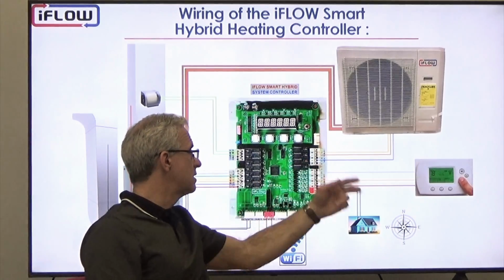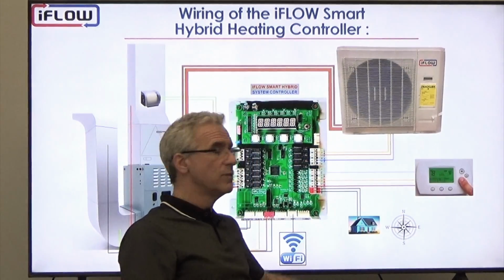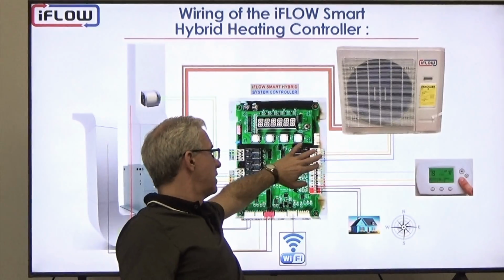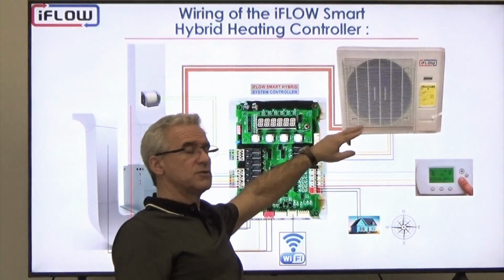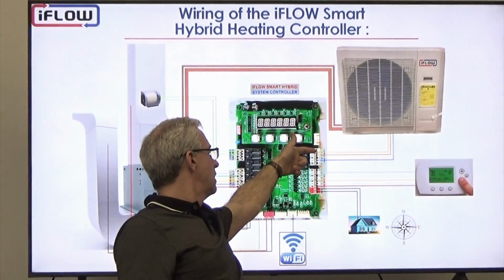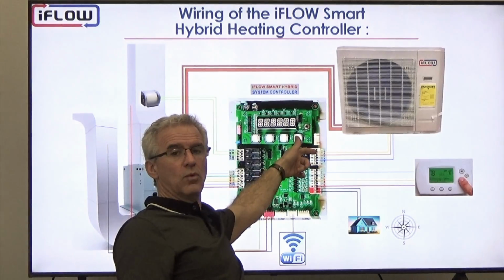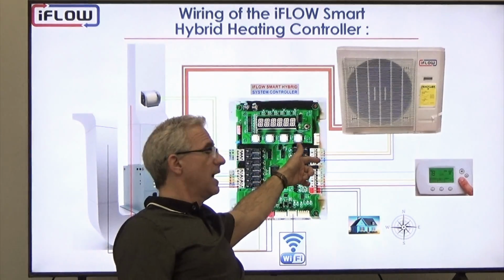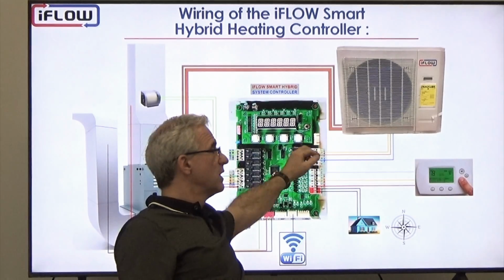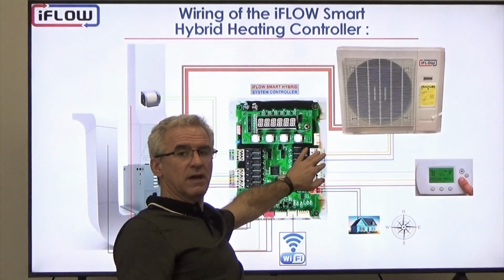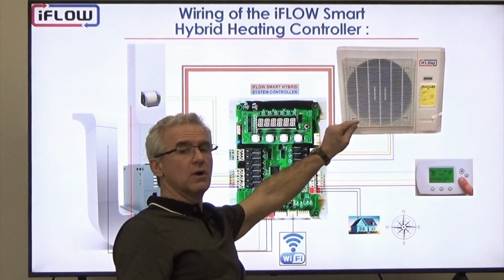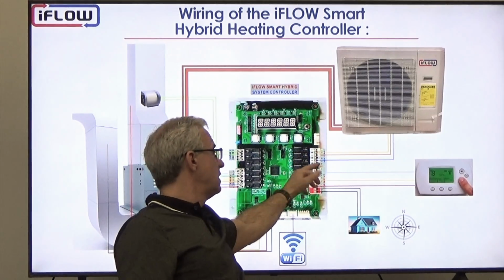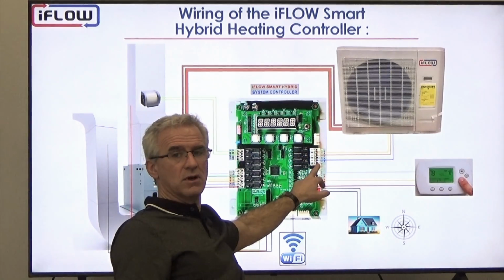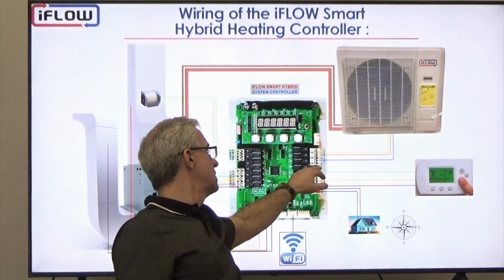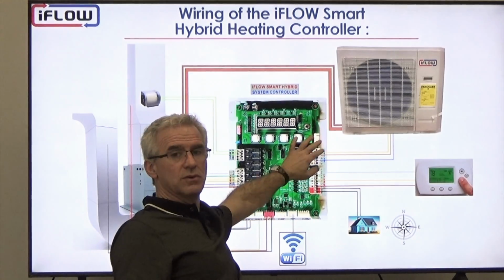And then wiring to the heat pump, if you're using the iFLOW heat pump that has just 3 wires to the outdoor unit, we're using the C, Y1 or Y, and a B or O. So 3 wires going from the iFLOW unit out to the outdoor. In some cases, you would need the R wire, which we also have the contact for. So we have R, C, O, B, Y1, Y2.